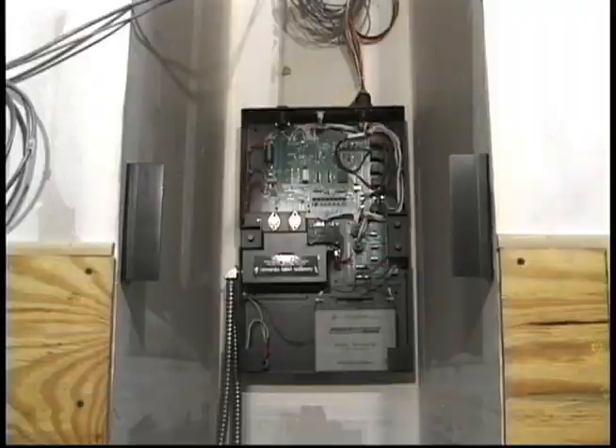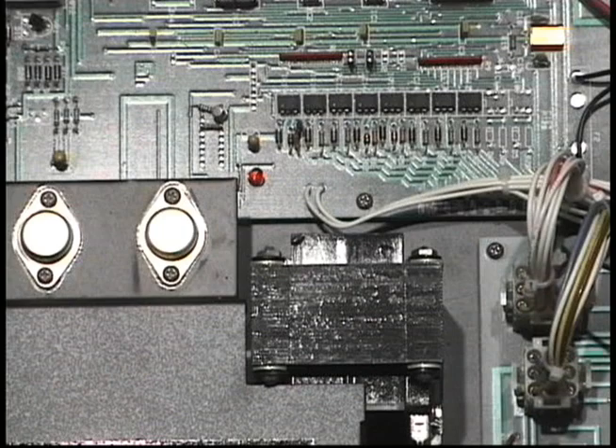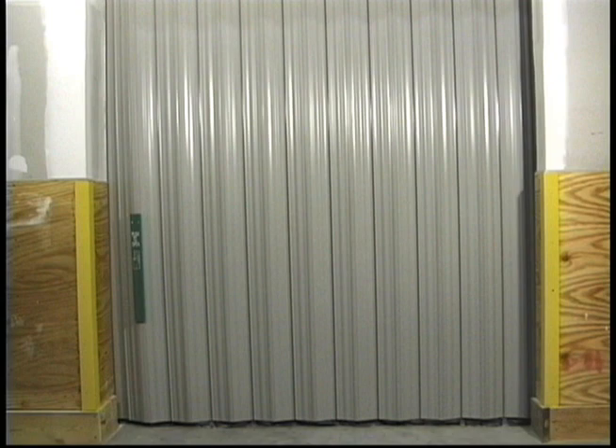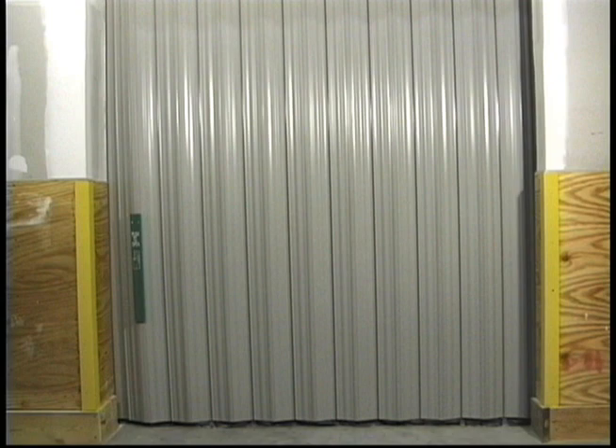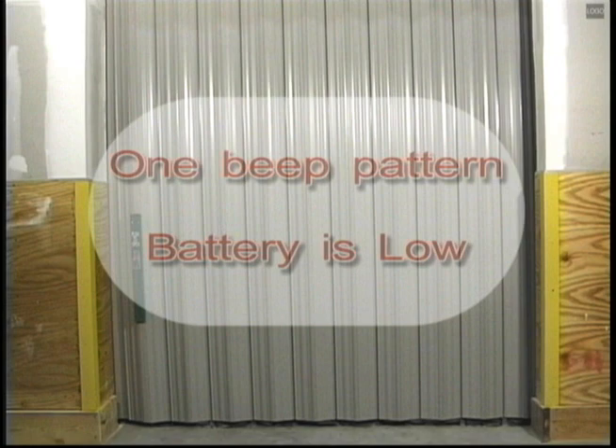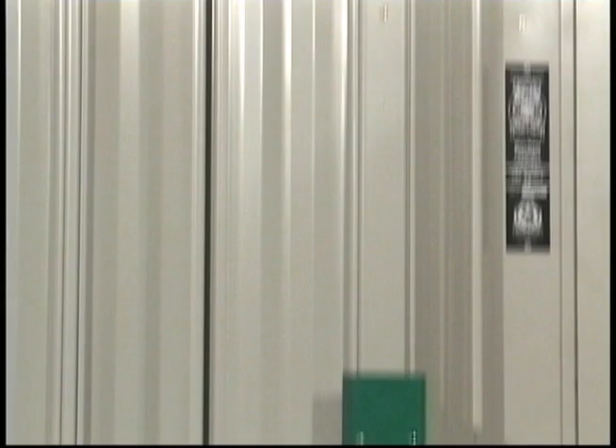If upon arriving at your building you find the door either in the open or closed position and you hear an audible fault signal, do the following. Listen carefully to the horn pattern. If it is a one-beep pattern, it is communicating that the battery voltage is low. This condition will occur if there has been an extended period of loss of AC power. There are two possible causes: first, a loss of AC power; second, a failed component in the power supply. Locate the open close switch on the lead post — notice it also has a mute position. The mute will temporarily silence the alarm while you contact the One Door customer service department for technical assistance. If the door is closed, reopen it with the lead post switch or push it back manually. As soon as the fault is corrected, the horn will automatically clear.